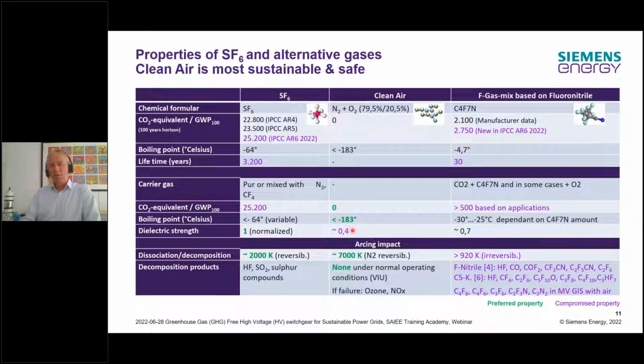And you see here on that point, the weakness of clean air is the dielectric strength. So it's less than 50% of SF6. That has to be compensated by design. I will show how this is done. You see it's also very stable, the air surrounding us. And actually, once in use, there are no decomposition products while switching or so on. In case of failure, there will be ozone, O3, which recombines very fast to O2 again, and NOx also, which is kept in the filter material inside.